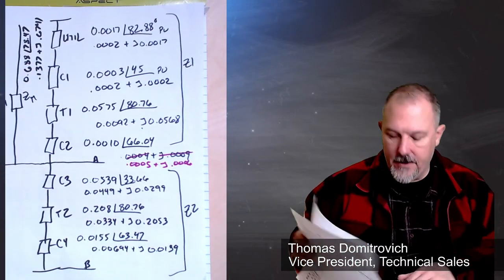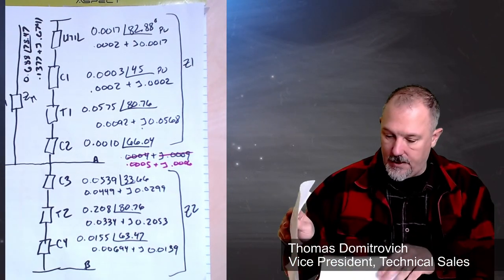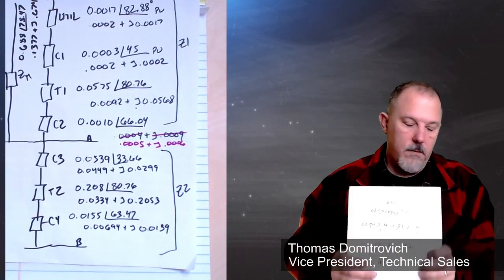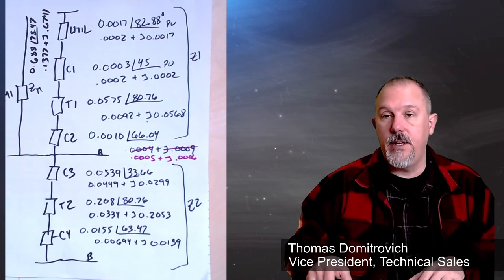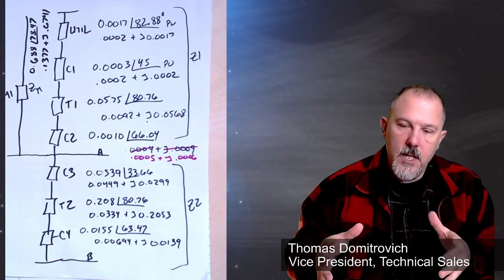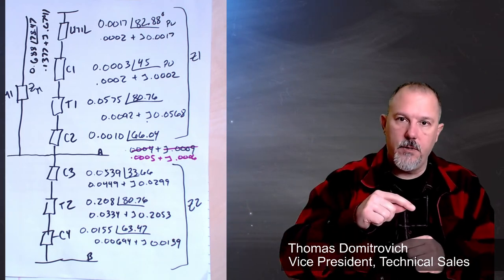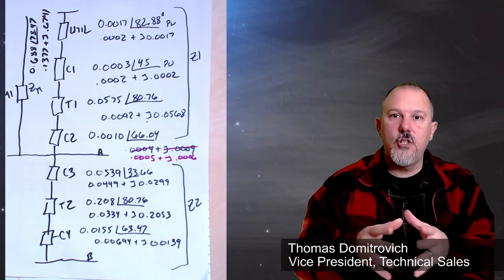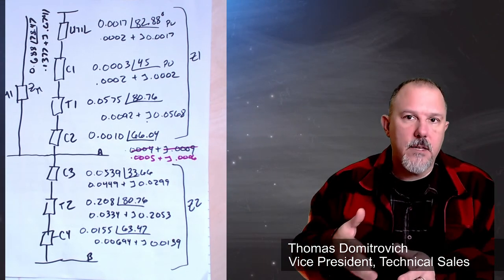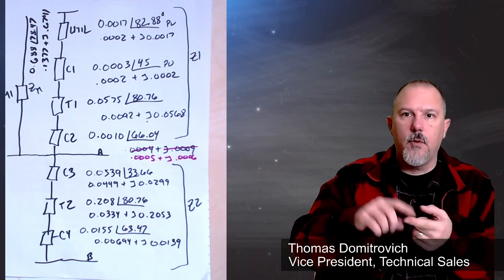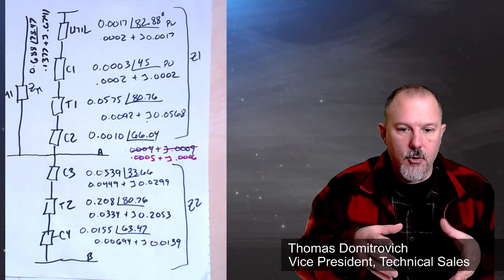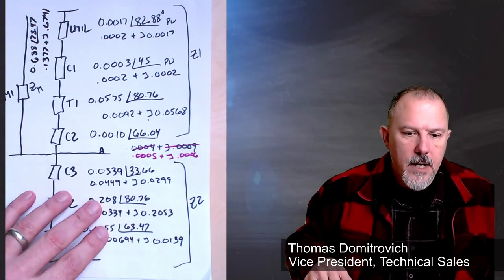That's our impedance diagram. It has all of the impedance values on it. Let's just talk about what we did. We took a one-line diagram. We converted every significant component into an impedance. Next week, I will go over why I picked what values, especially for the transformer. We'll talk about transformer impedances and X to R ratios, motor impedances and all that good stuff.